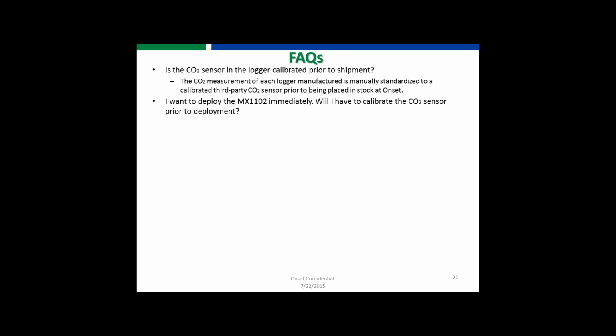Question came up, I want to deploy my MX1102 immediately upon receipt. As soon as I get it in the mail, UPS drops it on my front step, I want to use it immediately. Will I have to run a calibration, either a manual or an auto cal, prior to deployment? Our recommendation, yes. For the best accuracy, it's recommended that you do a manual calibration prior to your deployment, only because these sensors are optical in nature.